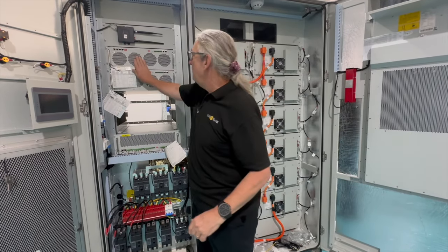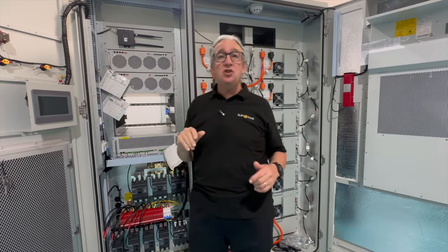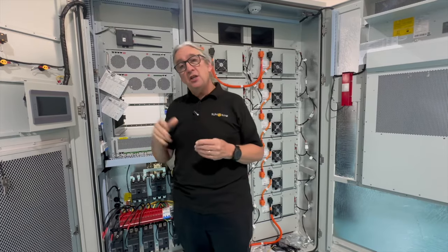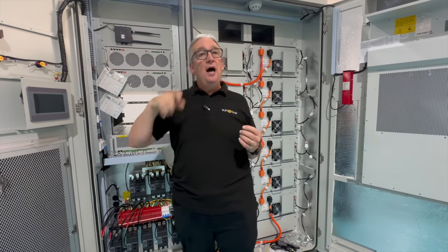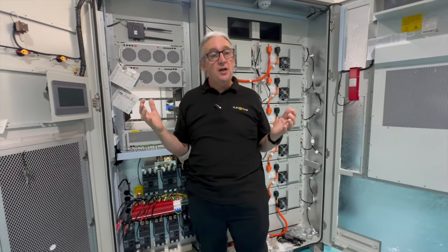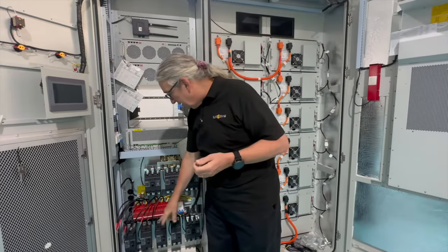The rest of this is your MPPT module. We have space to add an additional MPPT module if you want to. This one has 100 kilowatt, these are 50 kilowatt each, and this particular unit has 100 kilowatt MPPT split into 4 channels.